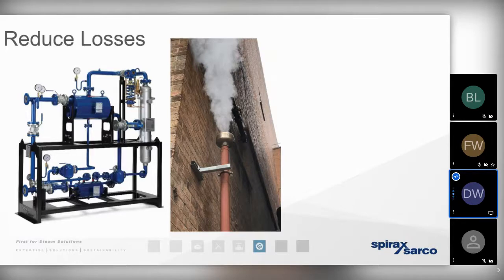The solution that you can see over towards the left-hand side of the screen is what we call flash recovery energy management equipment. So we take the flash steam, and we also take the residual condensate, if there's any that exists at the process, and we pass those two different phases across the different areas of a heat exchanger to add that heat energy to another heat sink. A perfect heat sink to add the energy to is going to be the boiler feed water. Not always possible, but we really need to think creatively with regards to where that flash steam exists and what we can do with that heat energy.